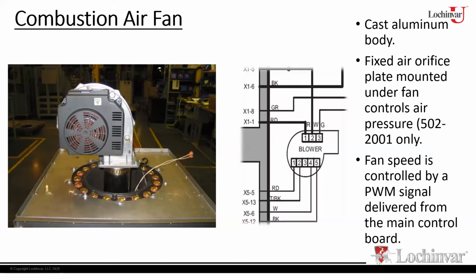We get back tons of blowers and control modules every year, and there's nothing wrong with them. Unfortunately, what happens in a lot of cases, people see the fan speed lockout, and the automatic assumption is it's a fan, and the fan gets replaced. And that doesn't fix the problem. Then they replace the next thing, which will be the control module. That's the next logical item. So you replace probably two of the most expensive components on the heater, and that's not been your issue.